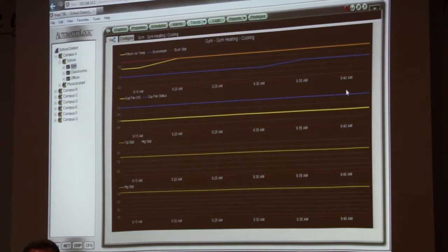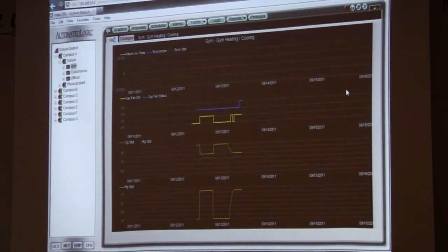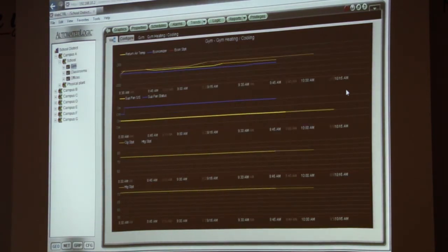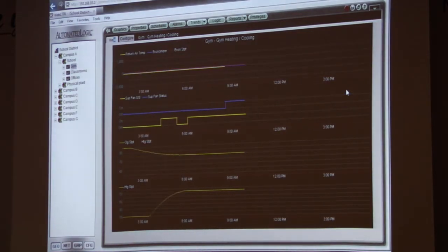So what you just did right there, you're saying, how can I move around the trend? Because that's what's going to happen. Somebody's going to say it wasn't acting right. So you're going to want to look at it really close. Remember what I said about the resolution. We want to look at it really close, and then we want to see what happened. This was the way to do it. I could use either the page up key on my keyboard or the page down. If I use the page up, I start to step farther and farther back from it. If I use the page down, I start looking in closer and closer. But eventually I see my problem was all the way to the left. What I'm looking for is over here.